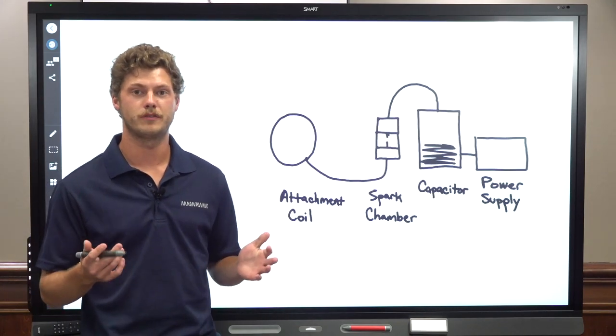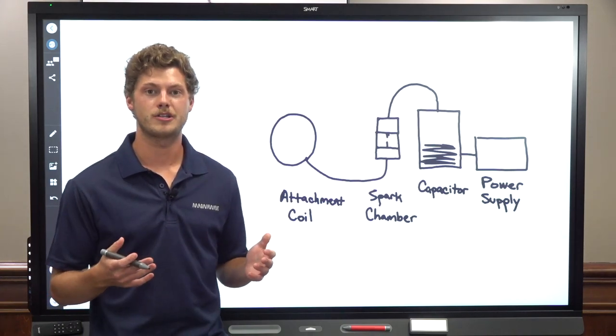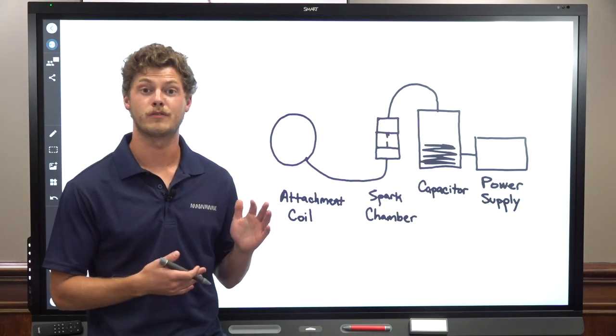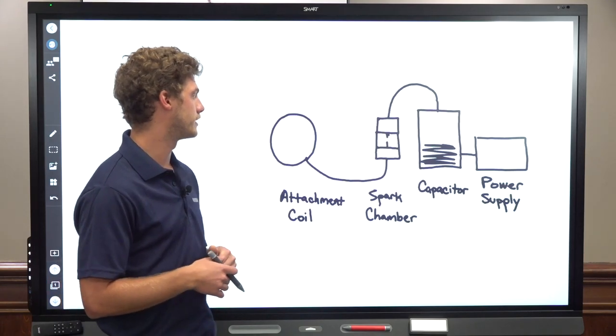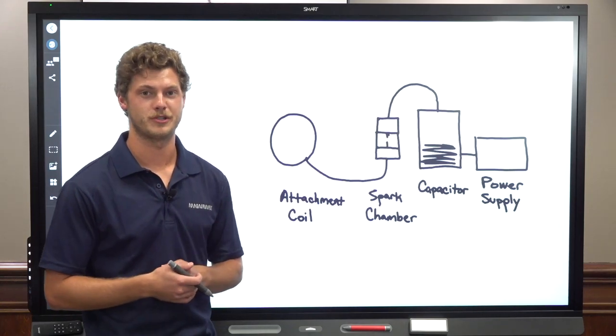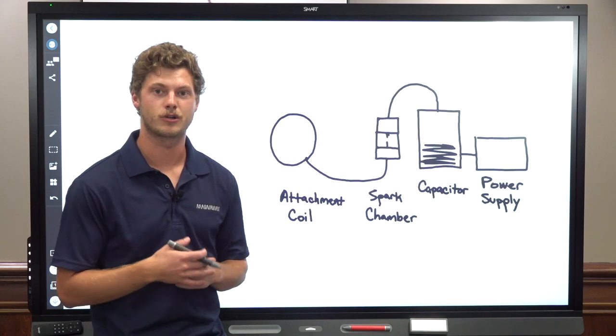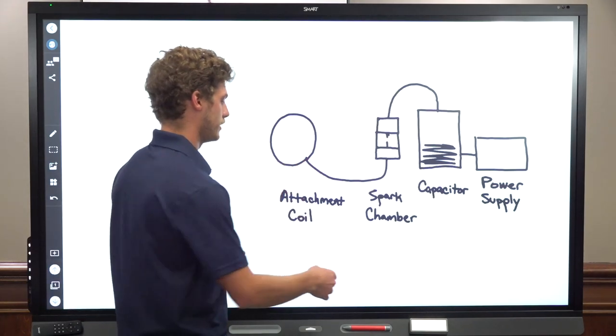The charge level of the capacitor is determined by the distance between the electrodes. As you can imagine, a larger distance between electrodes requires a higher energy or higher voltage in the capacitor before it will arc over. So you set your distance between the electrodes by setting the power level on your machine, at which point the capacitor will be charged up until it reaches the correct level, and all of that energy is dumped out through the spark chamber to the attachment coil.